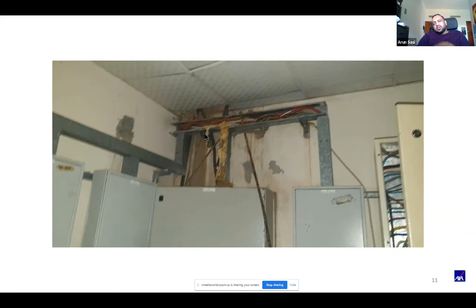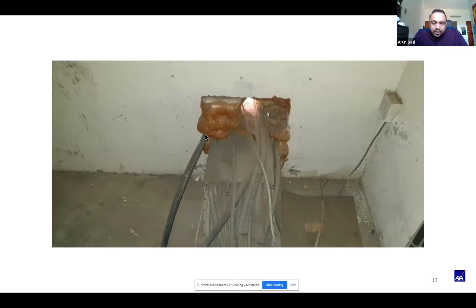Just explaining the part where cable penetration, duct penetration, and piping penetration, not just across firewalls, which are concrete walls with a specific definition, also across sandwich panels, especially the older sections, older buildings, which have combustible core insulations. So you can see very clearly that the insulation material that is used is not fire resistive. It's usually polyurethane foam, which you get in a can from the local markets. Now, again, as you can see, there has been some repairs done to even the polyurethane foam that they have used, and they have not bothered to fix it. In many of these situations, what happens is the cables lead directly into the factory, which means a fire starting in the electrical room can happily spread into the factory or the warehouse in question. So this is one of the issues with the combustible core that I've seen.